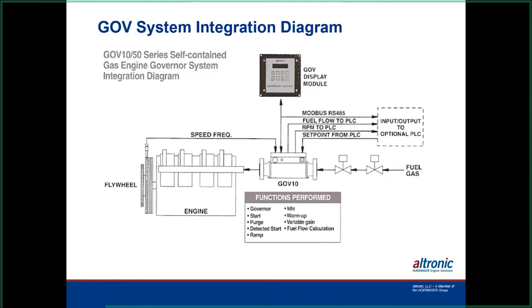And another neat thing about the valve is there's the governor part of the valve, and then there's also the starting part of the valve. The starting part of the valve will look at either a predetermined fuel pressure, or it will look at fuel flow. One of the nice things about fuel flow is on these big, large engines, when people are balancing the engine and they start pinching off these fuel valves and increasing the fuel manifold pressure, the pressure that was originally on it when you first programmed it may have increased by them restricting the flow of gas to it. By looking at the fuel flow number, that will always stay pretty much the same. So we give you the option of picking either the flow to do your light off on or the actual pressure. You can pick one or the other. Another really neat feature that's been added with some of the upgrades.